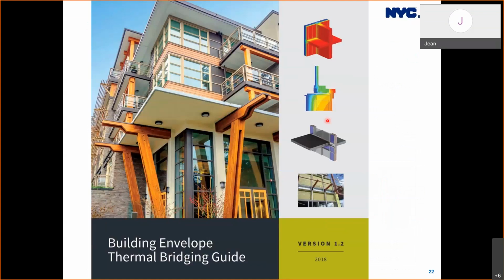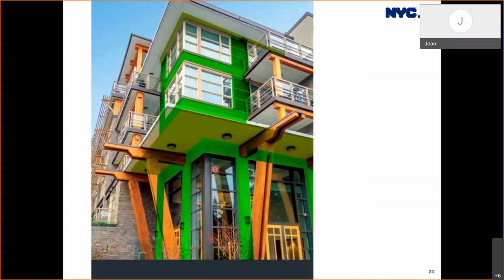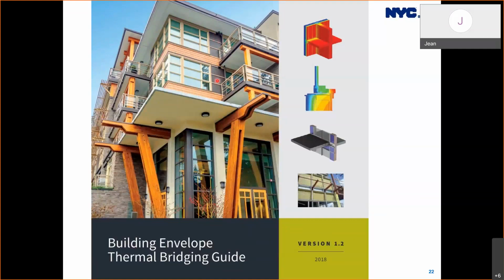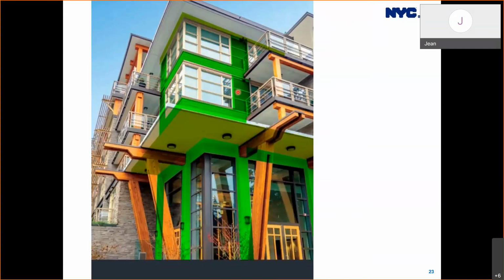If you look at the cover of this guide closely, a lot is going on in the building envelope and its thermal boundary. Maybe we could use this to identify those 3 types of thermal bridges with some assumptions, focusing on maybe here and here. So first, clear field thermal bridges: any typical walls, maybe even columns and soffit, and the spandrel walls. This is definitely a spandrel wall. It's an opaque wall, so it's not fenestration. These are the vertical components, but not only that, the roof and any slab components are normally clear field thermal bridges because they are normally interrupted by structural framing, or compromised by other assembly components.